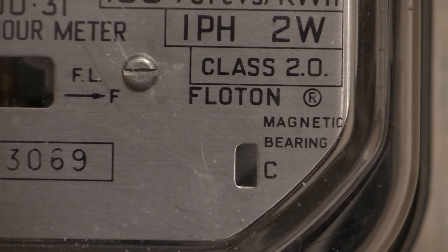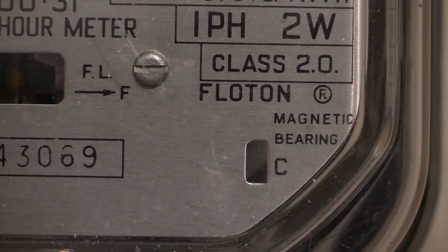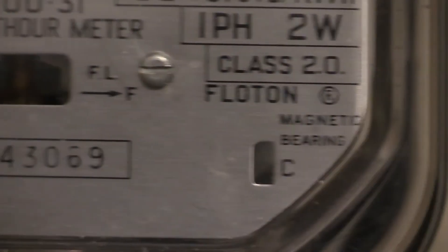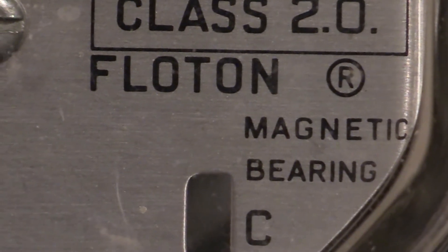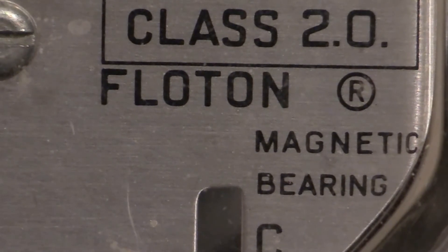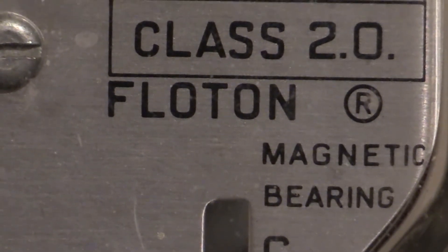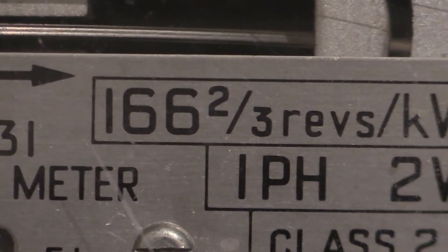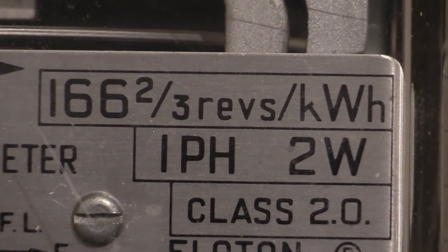Showing there is the Floton logo — Floton magnetic bearing, which is in reference to the load wheel. The load wheel in this one sits on the magnetic cushion and therefore maintains its accuracy over a very long time. There is the load wheel speed: 166 and 2/3 revs per kilowatt hour.